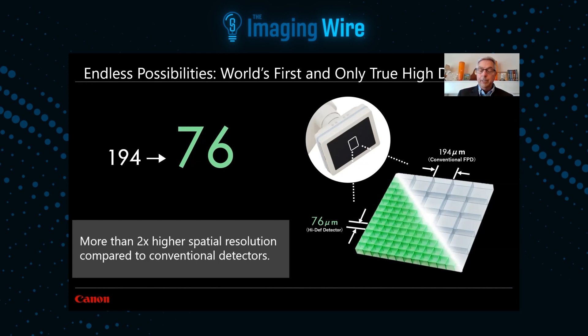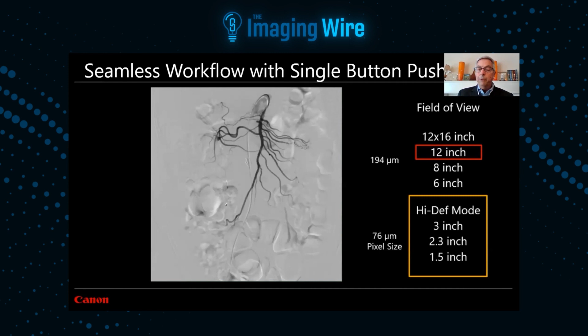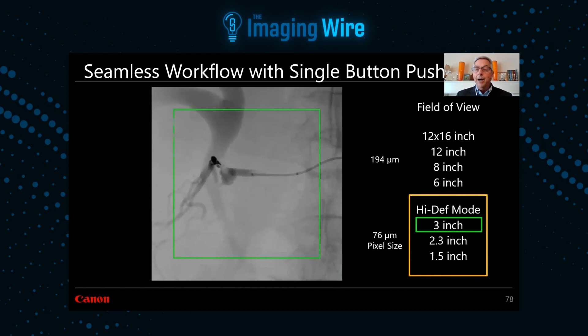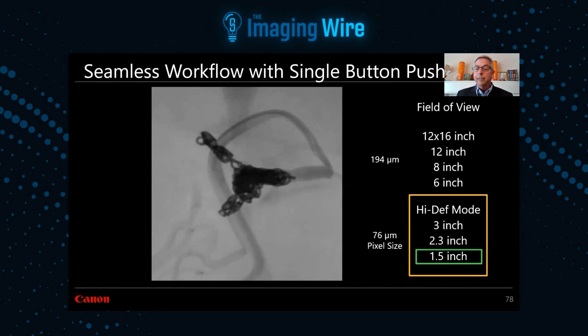So if you were to look at a flat panel detector that's got different mag modes that you can see over here on the right side of the image that are the standard view modes. Well, now with this HD76, you get 3 extra mag modes that allow you to step through your mag modes. And now you go into a high resolution that's over double the resolution, all the way down to a 1.5-inch mode. And so you can really zoom in on a device or an area in the anatomy on the patient.